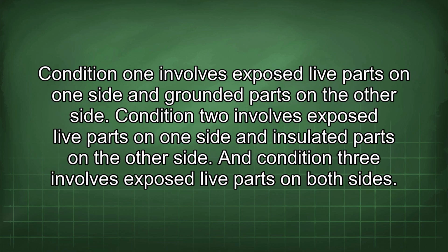Condition 1 involves exposed live parts on one side and grounded parts on the other side. Condition 2 involves exposed live parts on one side and insulated parts on the other side. And condition 3 involves exposed live parts on both sides.